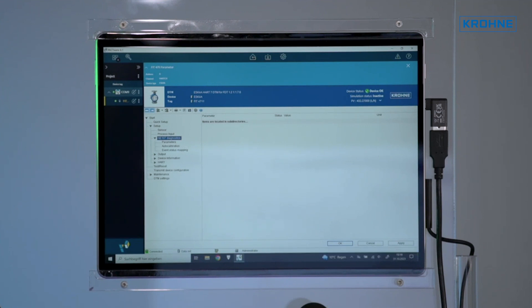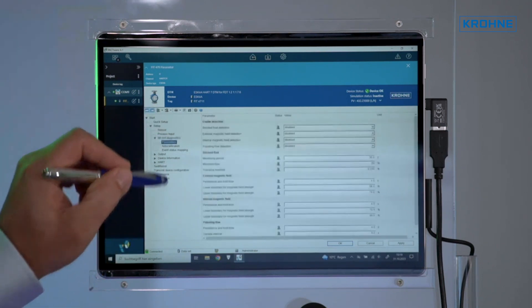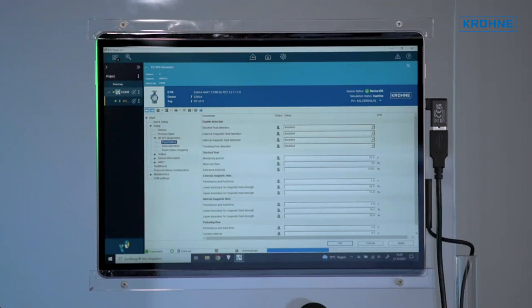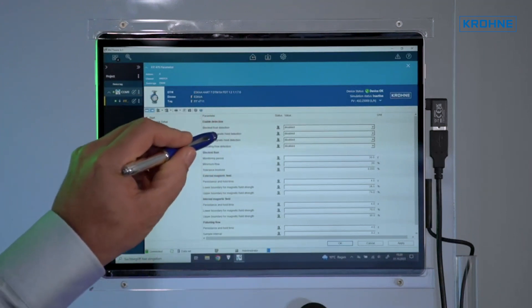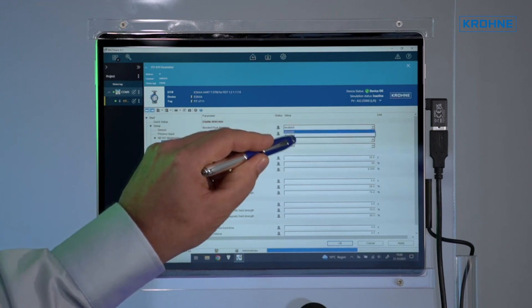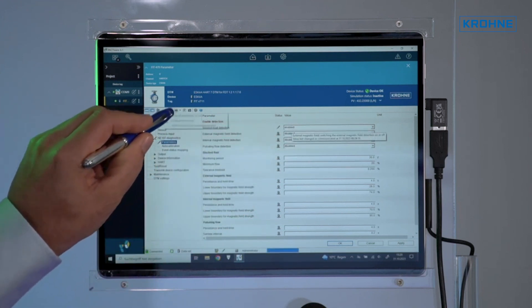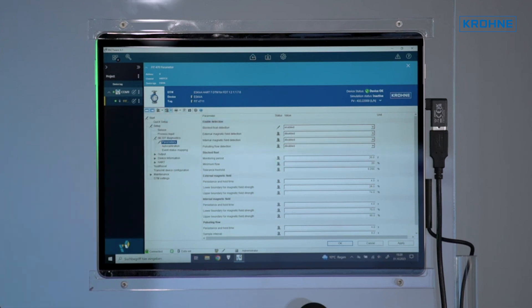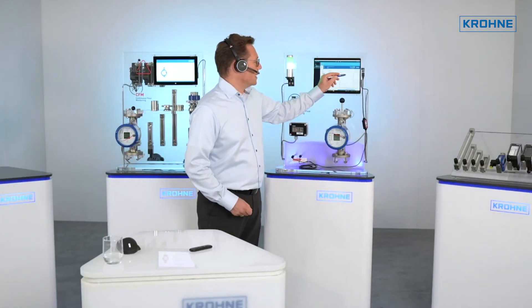We introduced this about two years ago. The first thing we can do is add parameters to enable one of the diagnostic functions — the first one is the blocked float detection. I will enable it and write it down to the device. Now I have enabled the float blocking detection with a certain parameter set.